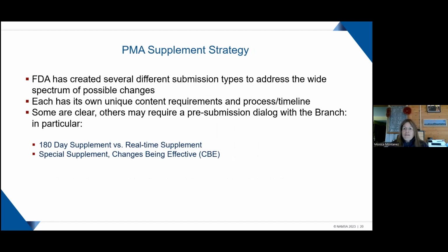FDA has created several different submission types to address the wide spectrum of possible changes, and each has its own unique content requirements and process timelines, as we depicted earlier. Some are clear, others may require a pre-submission dialogue with the branch. Initially, I contact the branch lead reviewer via an email before jumping into the pre-submission dialogue. But some of the submissions that may require this type of conversation are a 180-day supplement versus a real-time supplement, or a special supplement, changes being effected. Coming up, we will be discussing the PMA special supplement, changes being effected.